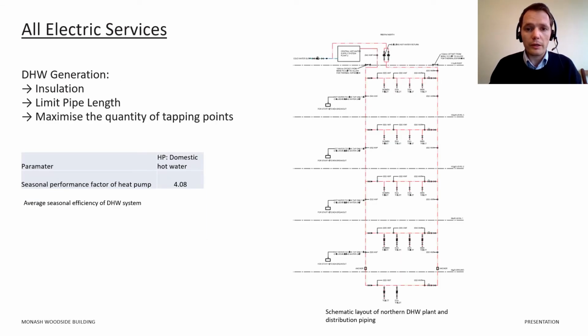To further limit the PER demand, the domestic hot water generation system was designed to reduce system losses. This means that it's well insulated all the way through up to the point of use. The building has two 15 kilowatt CO2 heat pumps, which have been strategically placed as close as possible to the riser, limiting the vertical runs of the circulation piping. The same riser path is also used to limit the length of accumulated single pipe runs, and lastly, the maximum number of tapping points are used per riser. All these seemingly straightforward design decisions have a significant impact on the domestic hot water system's PER demand. It's worth noting that the CO2 heat pumps provide excellent energy efficiency. In this case, it has a seasonal performance factor of 4.